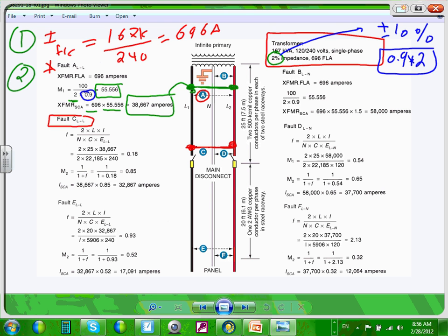line to line. Can you guys see that this is 25 feet away from the transformer? And we're using two conductors, 500 kcm each. So I found the short circuit at the terminal of the transformer right here. I shorted them, right? There's the short circuit right at the transformer.